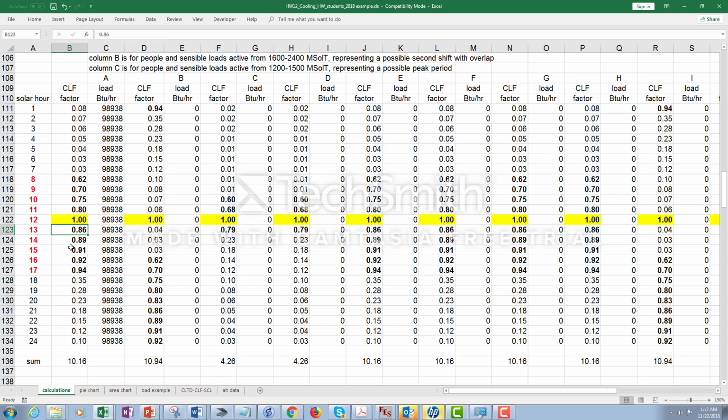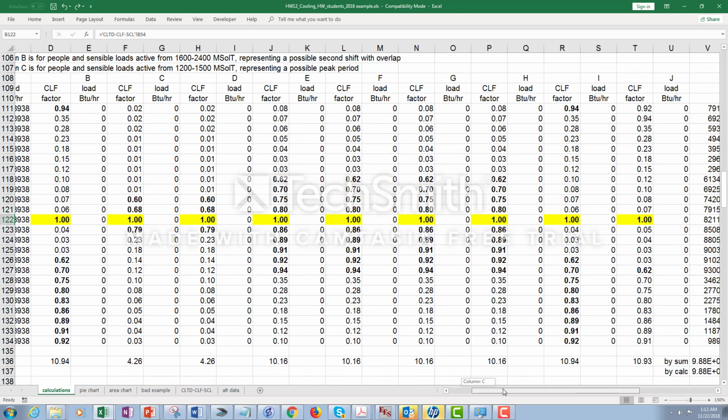Notice these cooling load factors just account for smearing 10 hours into 24 hours. So it should add up to 10. If I go back to the number that I'd already put, that's 83. That agrees with the table. It's numerically 10 hours, and that's all sensible heat.